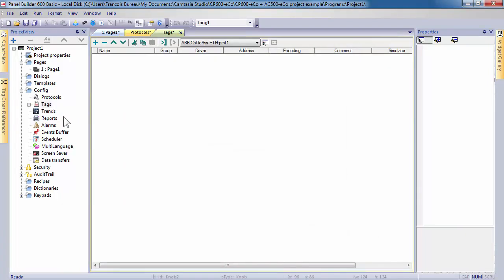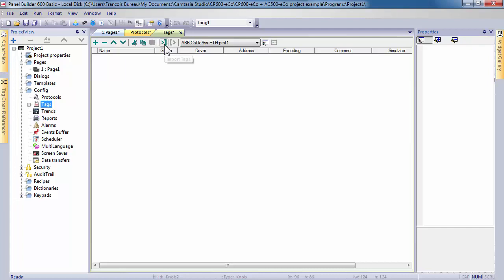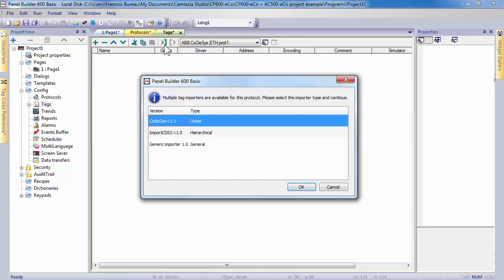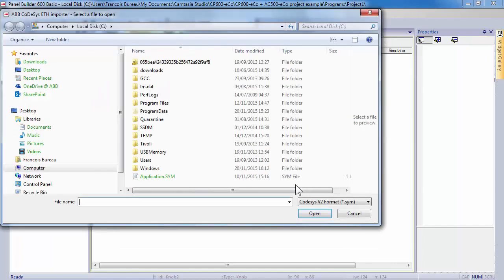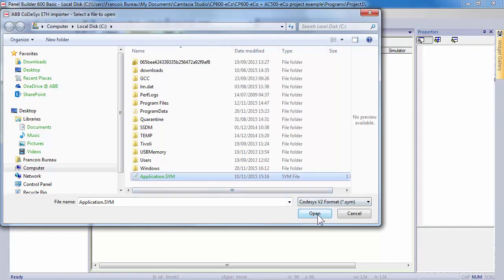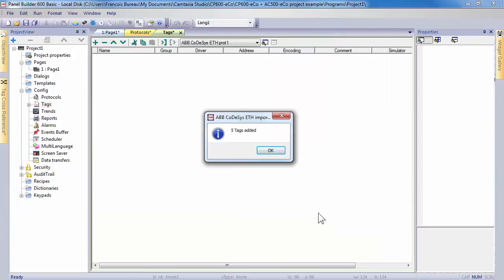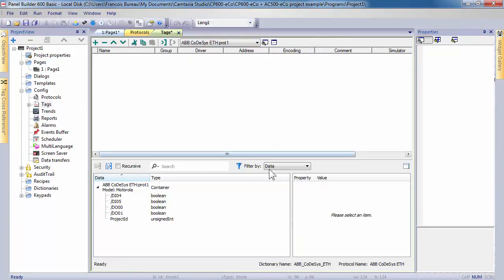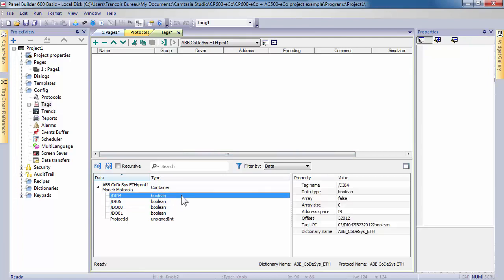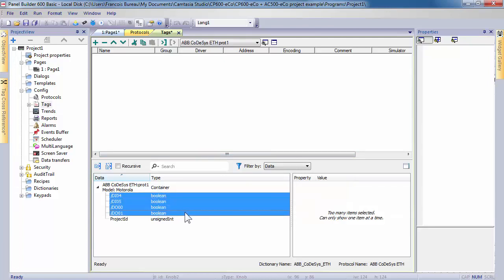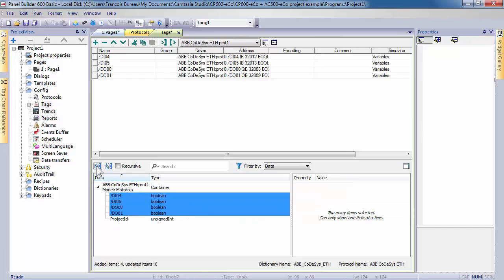The second step is the definition of tags. The software mechanism uses them to access all device data. The tag editor can be used to create and manage all tags of your project. For an easy creation, click on the icon import tags in menu toolbar of the tag editor and follow up the next instructions. Look for location on computer where the previously created symbol file has been stored, and import it in tag editor. Now in lower part of tag window, you could decide by selecting one or more tags, which will be imported in your project. After importing action, the tags are copied to the project and listed in the upper part of the tag window.